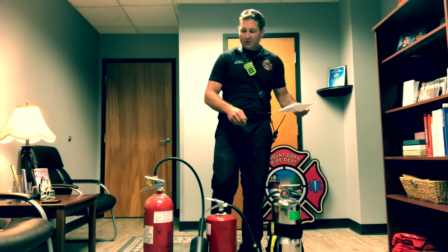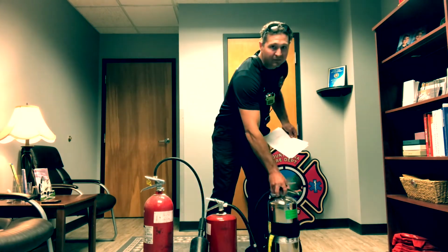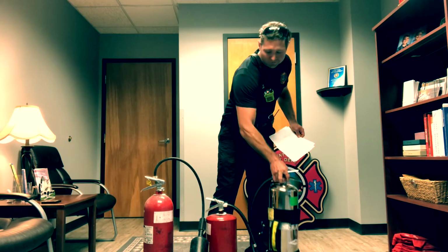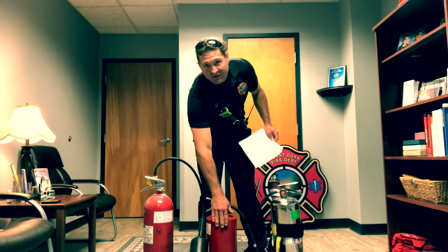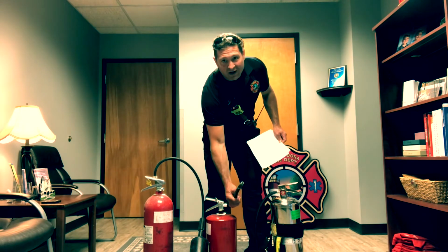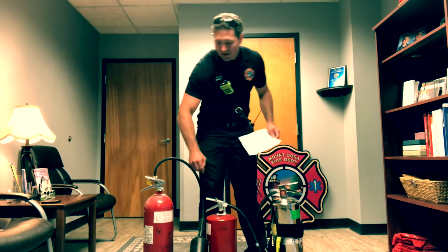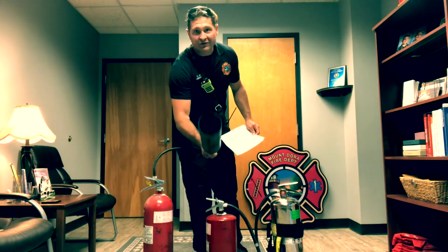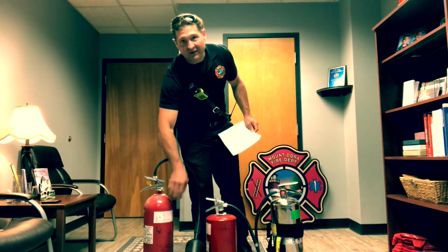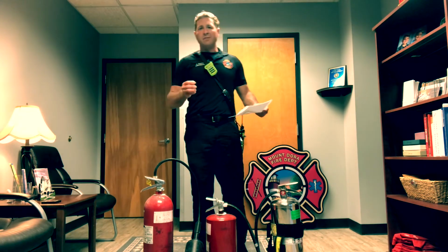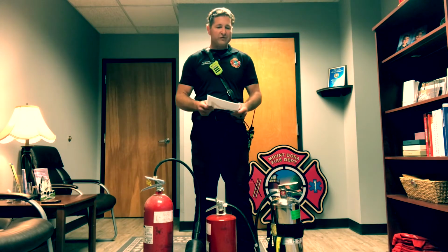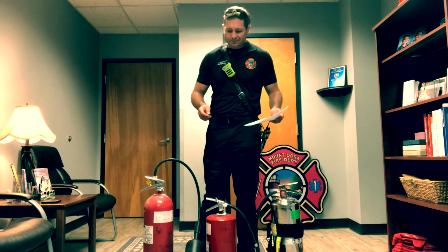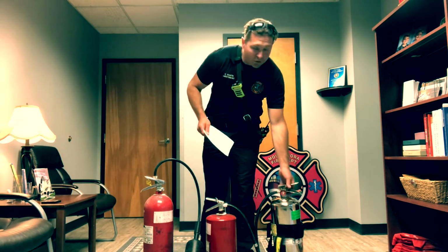In order to extinguish those, we have 3 options. One being a water can, which simply provides pressurized water, an ABC extinguisher, otherwise known as a dry chemical extinguisher, probably your most prevalent, and a CO2 extinguisher, which has compressed carbon dioxide gas. Depending on the particular burning substance you're dealing with, will depend on which fire extinguisher is most appropriate. For ordinary combustible materials, Class A, water would simply work.